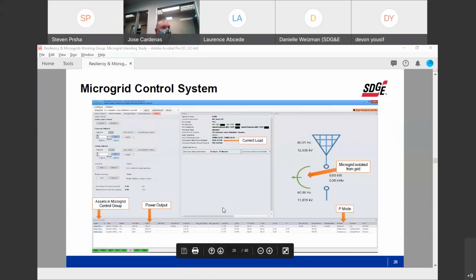I can start. The first question was around the Borrego microgrid: is there a need to curtail the distributed generation, NEM generation, and if so, how is this accomplished? No - as we mentioned up front, NEM is a passive microgrid resource. Any behind-the-meter NEM resource is going to behave according to its pre-programmed behavior. We do see some issues with old style inverters not having great ride-through capabilities, and they can all reconnect at once. So it depends, going back to the planning assumptions we mentioned earlier. But no, nothing happens to NEM resources - they just behave as programmed.